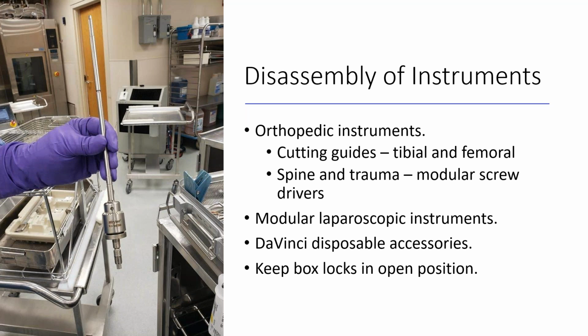Even with the most basic instrumentation, an Alice, a Coker, any of those things, they all have box locks that are very difficult to clean, and they can be clamped shut, but we need them in the open position in order to clean them appropriately. We've had scenarios where the OR clamps all these instruments for their procedure so that when they hand them to the physician, they're in the right position. But if you forget or fail to open up those box locks, that can cause a serious delay in getting those instruments clean for the SPD techs.